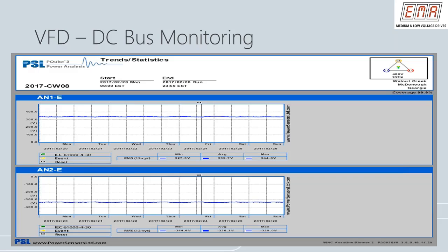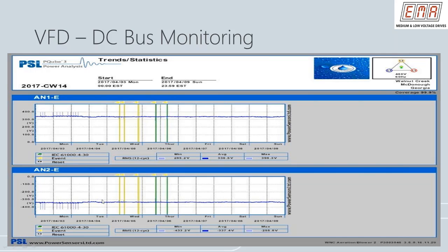Well, in that particular case, the drive was so badly damaged, we could not do a good forensic analysis on the drive, and so we offered them this tool, this drive scan, to install on the adjacent drives, because their concern is, well, we may lose other drives because all these drives are about the same age. Well, as you can see here, we're looking at the DC bus of the drive. This was back in 2017. So everything looks good on the adjacent VFD, and then like I said, this one was in February.